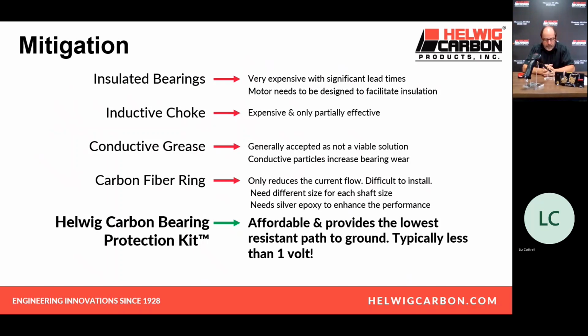What does Helwig Carbon do? We do things a little bit different here. We put a silver graphite brush with a spring behind it and maintain force on the shaft. Remember, the force is everything. That means the day we put it on, it will work as well as it will 5 or 7 years down the road, when it's still maintaining contact. It's very important to know that the contact is everything. Silver graphite is a very, very low friction, very, very low resistance product.